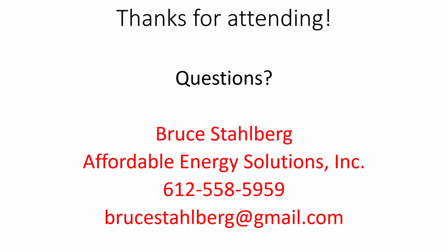I have a question. There's a move towards installing heat pumps, and those supposedly require a lower temperature rise and therefore need a greater airflow. Is that causing a problem with ductwork? Yes, thanks, Tim, for asking that question. It's kind of why it's important that we do some measurements, because when we're installing new systems, we are not changing the ductwork, generally speaking. We're using the original ductwork.